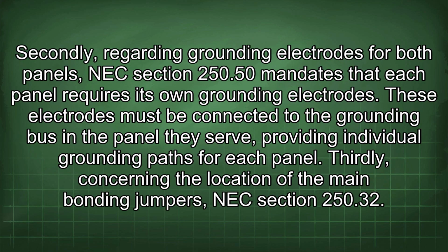Secondly, regarding grounding electrodes for both panels, NEC section 250.50 mandates that each panel requires its own grounding electrodes. These electrodes must be connected to the grounding bus in the panel they serve, providing individual grounding paths for each panel.